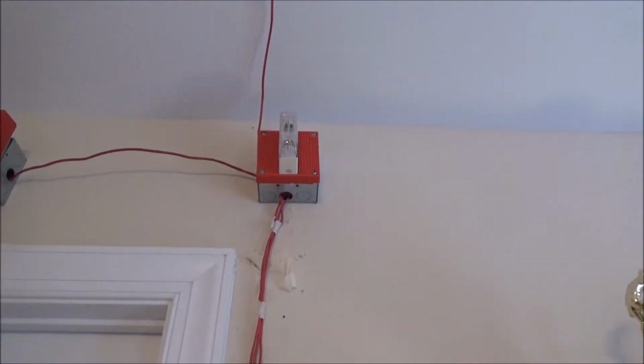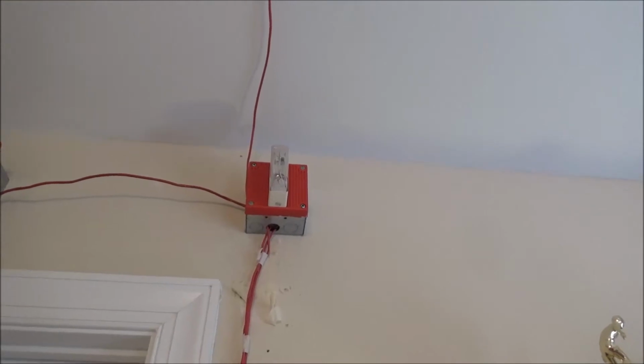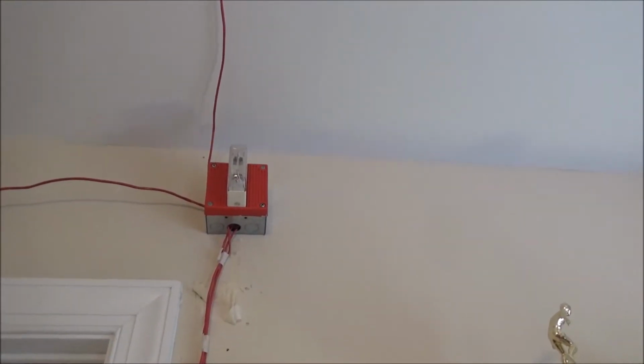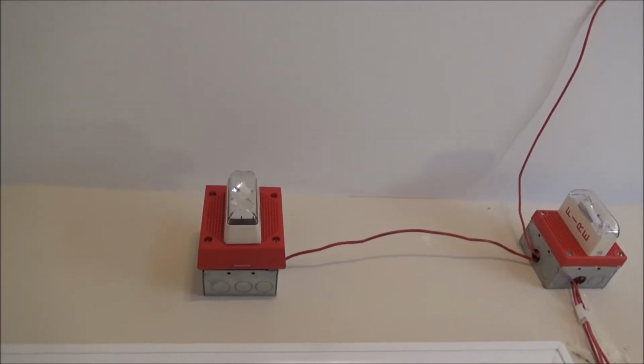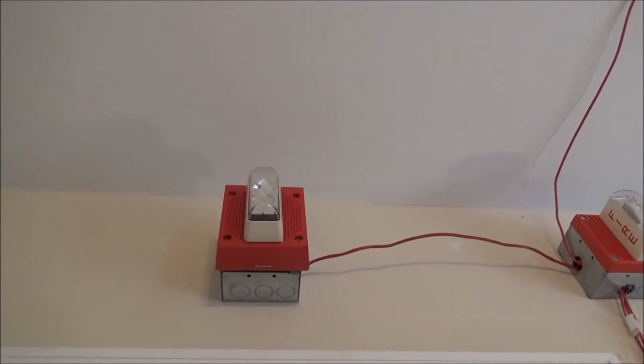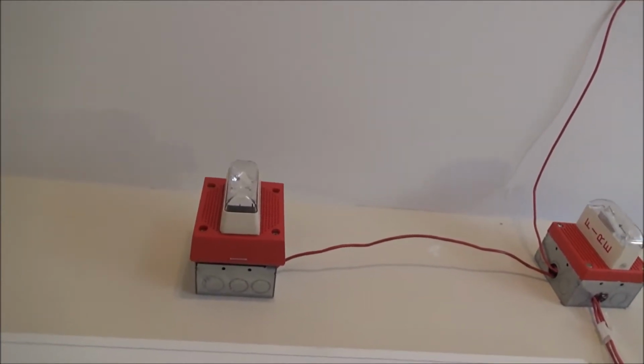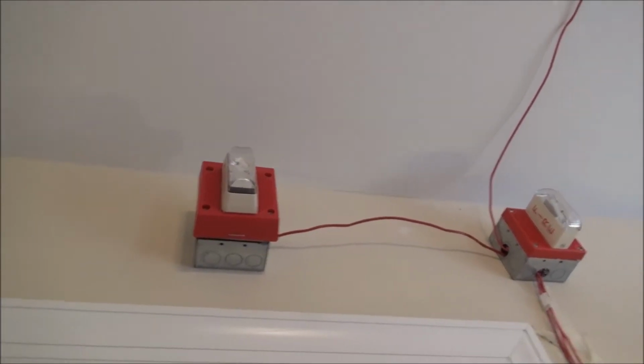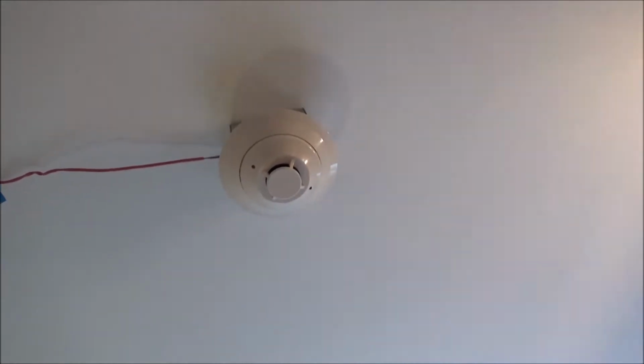You've seen my MT424 LSM before. Nothing new there. It's set on high volume continuous and the panel is coding it to March time. For the second notification appliance, we have the Edwards Pre-Integrity 7927A006, and it is also being coded to March time, and I have tuned it so that it sounds exactly like the regular Integrity. On the ceiling, we have the SD355 as usual.